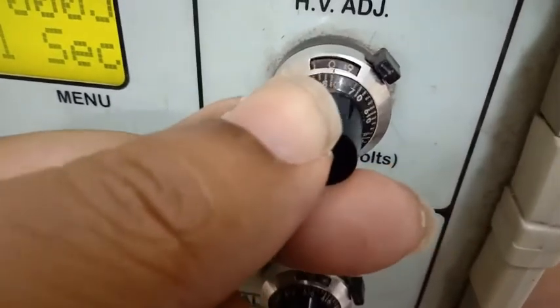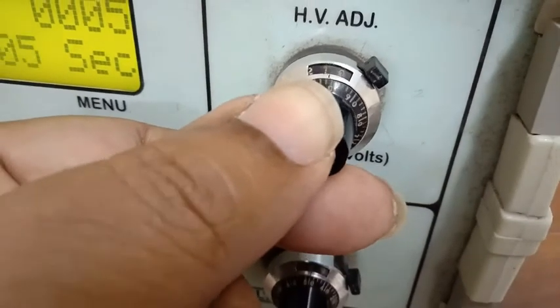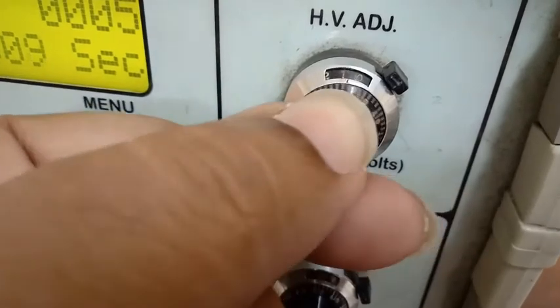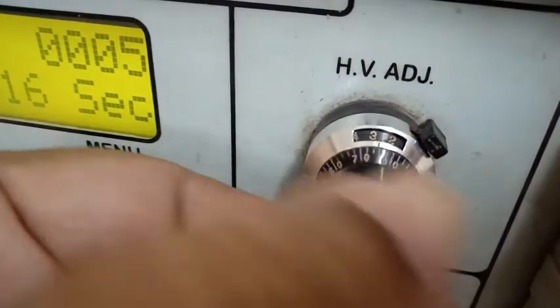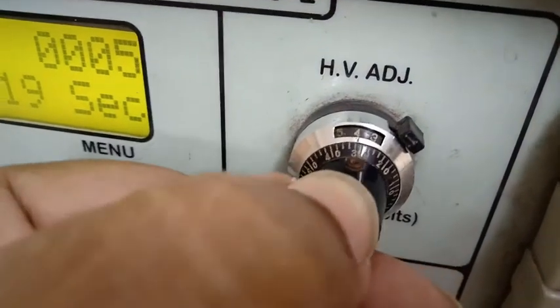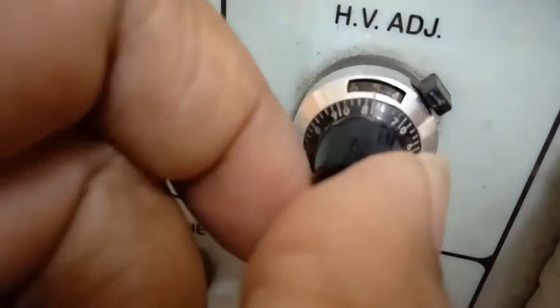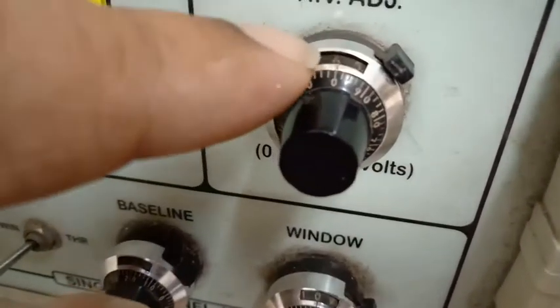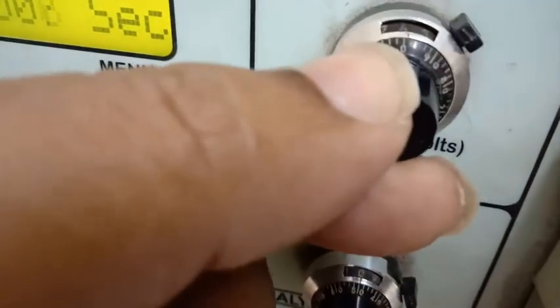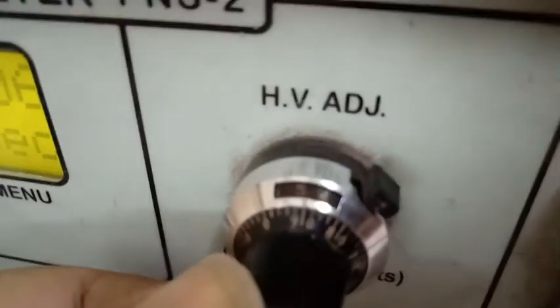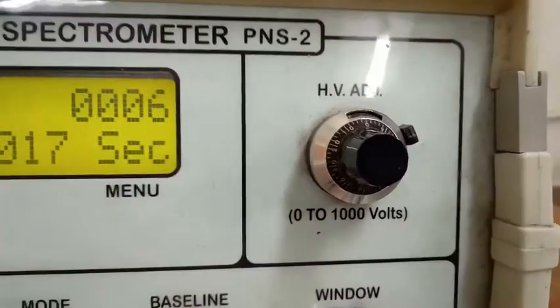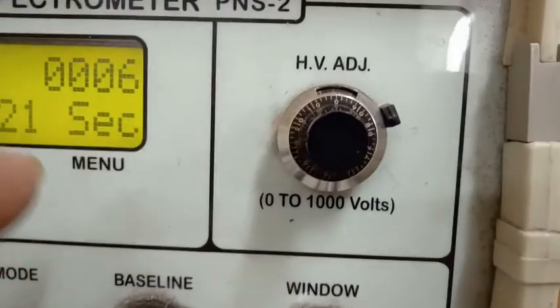Okay, 1 turn makes 100 volts, and so 200, 300, 400, 500, and then 600 volts. Okay, so this is the detector operating voltage. This 6 shows 600 volts, and if we give this, then this is 590 volts. Okay, now the operating voltage is 600 volts. Now we lock it like this. This set can give us up to 1000 volts.